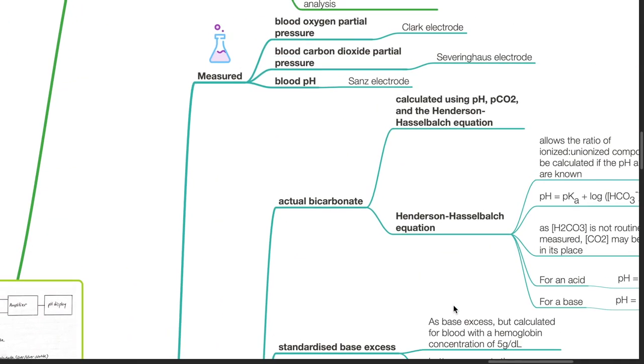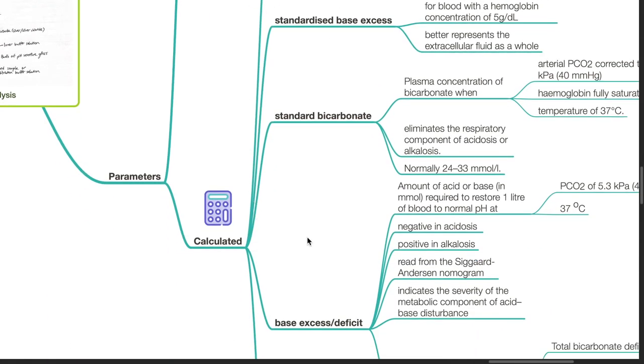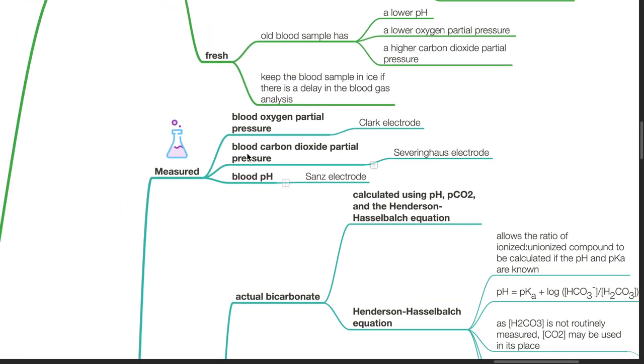Parameters analysed includes those that are measured directly and those that are calculated. Blood oxygen partial pressure is measured directly using the Clark electrode. Blood carbon dioxide partial pressure is measured by the Severinghaus electrode, and blood pH is measured by the Sanz electrode.